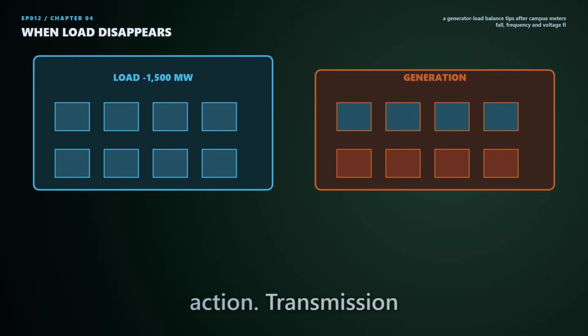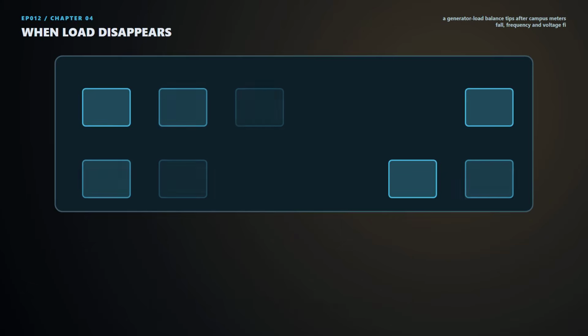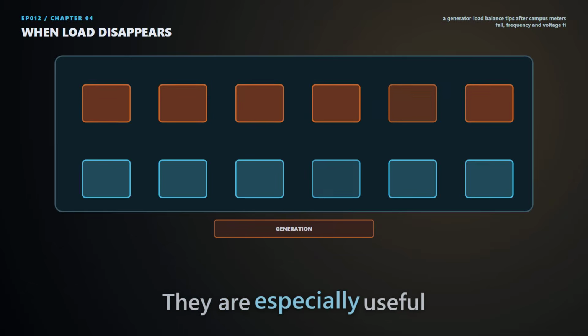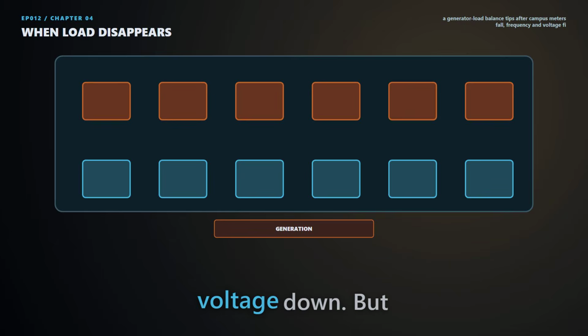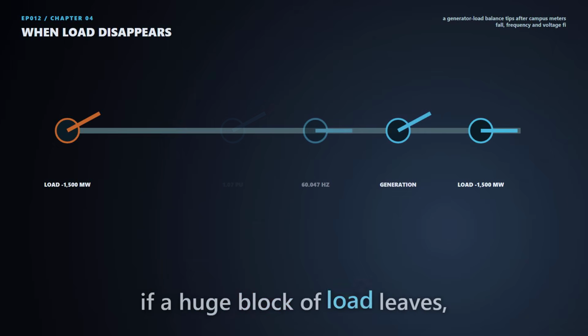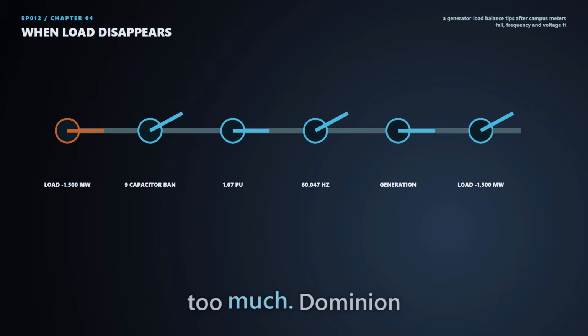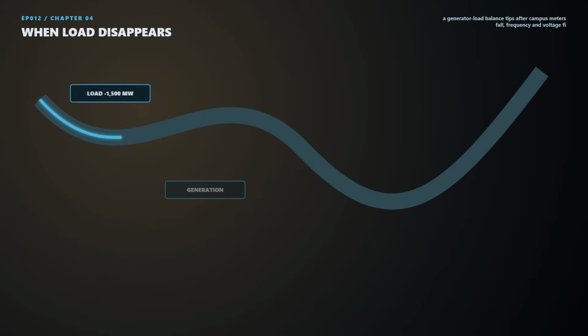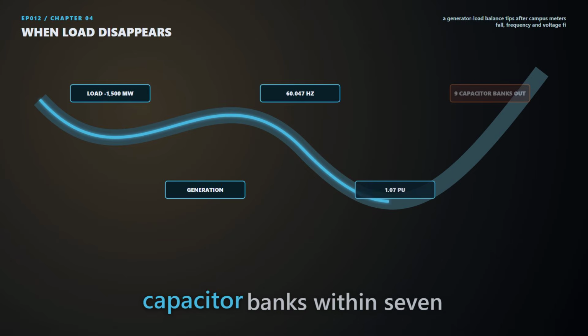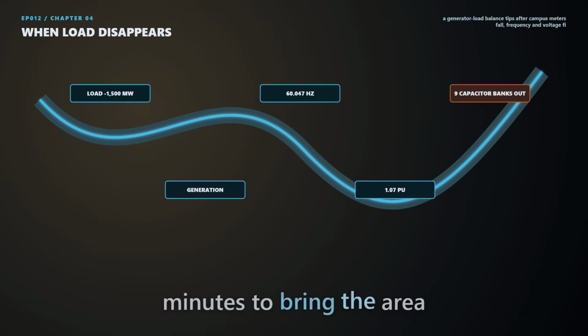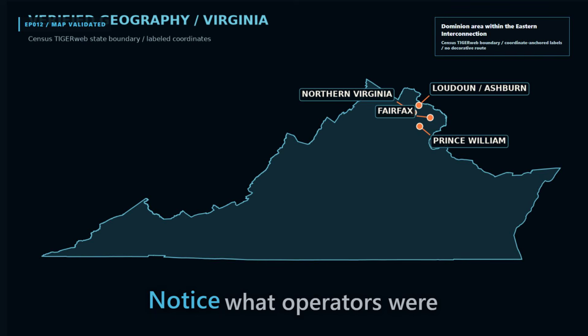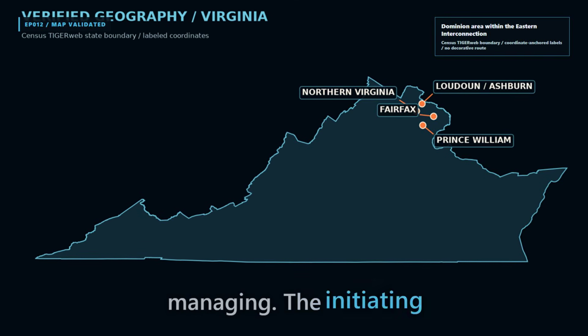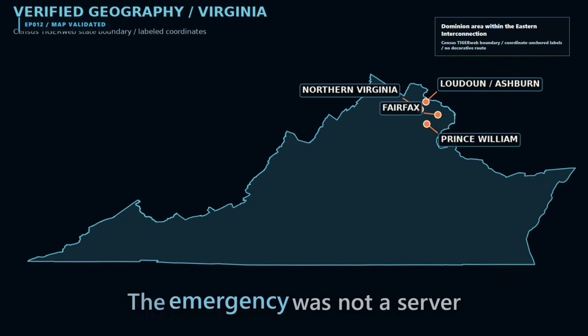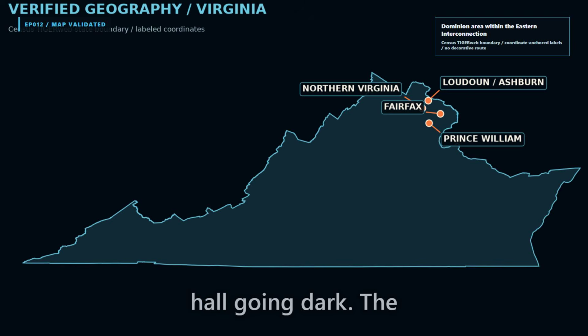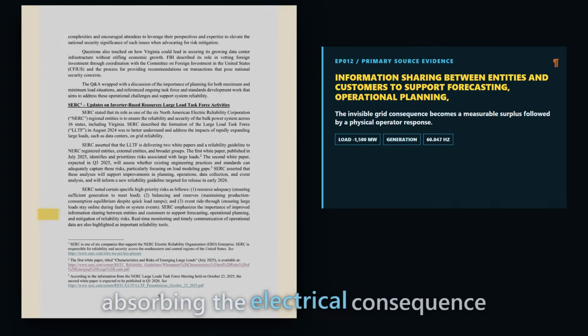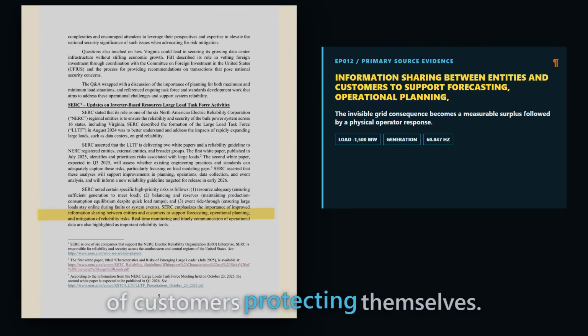Transmission systems use shunt capacitor banks to support voltage. They are especially useful when heavy power flow pulls voltage down. But if a huge block of load leaves, the same support can become too much. Dominion reported that operators removed 9 230 kilovolt capacitor banks within 7 minutes to bring the area back toward nominal voltage. Notice what operators were managing. The initiating fault had already been cleared. The emergency was not a server hall going dark. The operational task was absorbing the electrical consequence of customers protecting themselves.